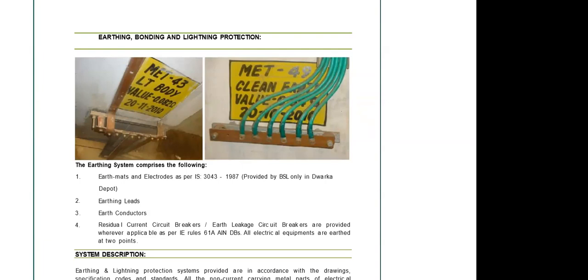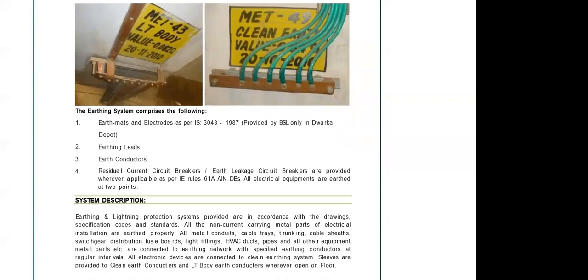So what are the considerations for earthing system? Generally, for an earth mesh, it is basically a large type of earthing where we provide, for example, say 100 meter by 15 meter of complete earth mesh. Generally, it is done through round bars, with the bars connected to create a mesh, and from there the earth strips come out. The relevant standard for doing the earthing is IS 3043, and earthing leads and earth conductors are also there, and residual current circuit breakers are also provided, mostly in case of single phase earthing.